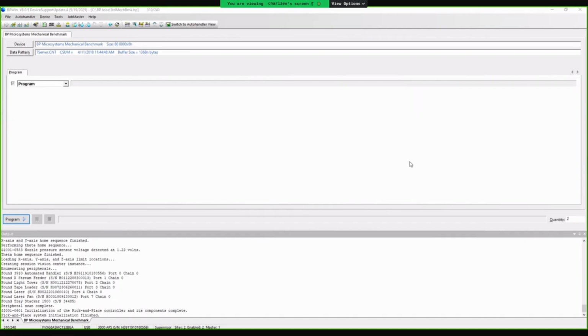In fact, Charlie, when the machine initializes, my understanding is it does go through the calibration process to make sure that everything is set properly. Yes, it does. The initialization of the machine basically checks the hardware, and if the initialization will pass, then the hardware is in good enough condition to run a job.